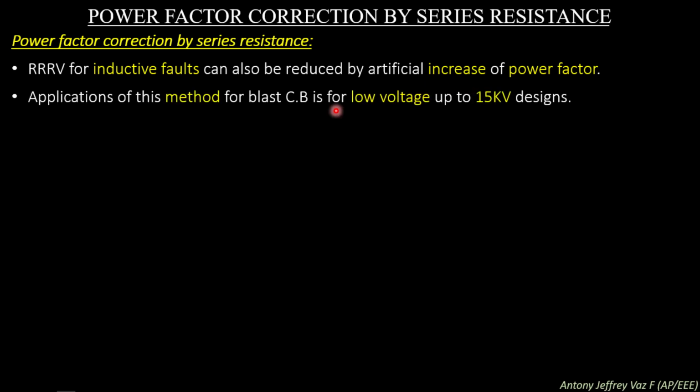Application of this method is for blast circuit breakers and is for low voltage up to 15 kilovolt design. So this can be used only for low voltage designs up to 15 kilovolt, and this type of power factor correction by inserting series resistance, or by increasing the power factor, can only be used in blast type circuit breakers, that is air blast or oil blast circuit breakers.